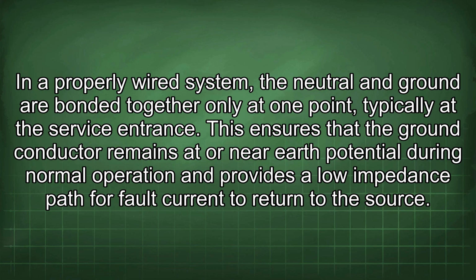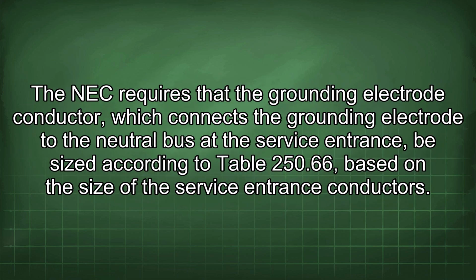This ensures that the ground conductor remains at or near earth potential during normal operation and provides a low impedance path for fault current to return to the source. The NEC requires that the grounding electrode conductor, which connects the grounding electrode to the neutral bus at the service entrance, be sized according to Table 250.66, based on the size of the service entrance conductors.